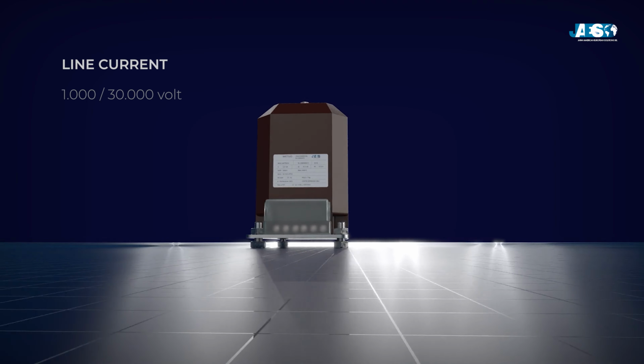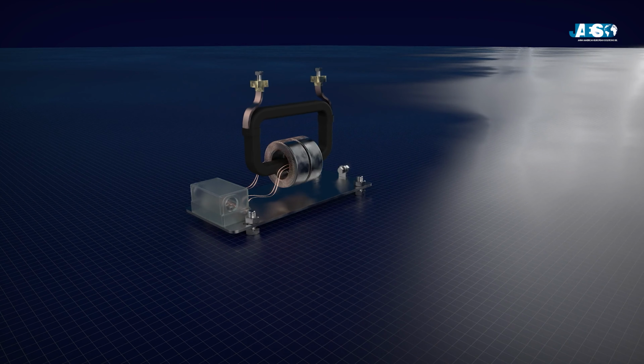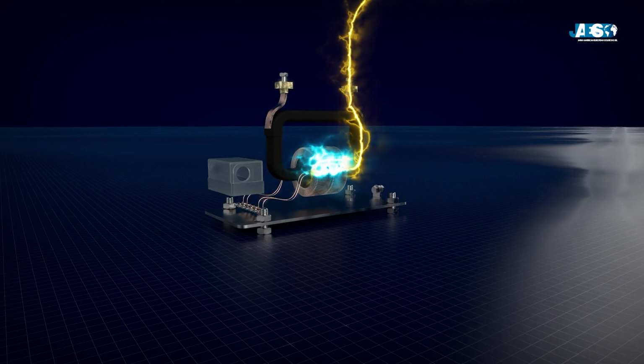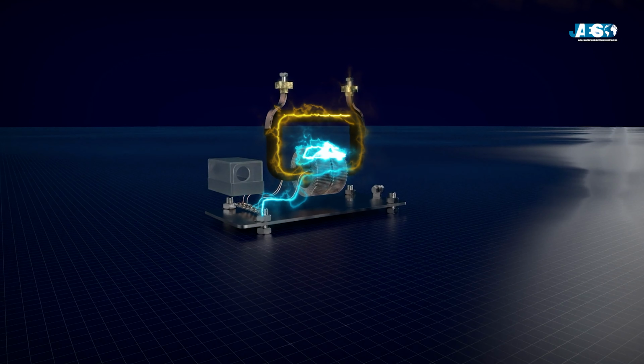They are basically inductive sensors consisting of a primary winding, a magnetic core, and a secondary winding. Essentially, a high current is transformed into a lower one using a magnetic circuit, so very high currents can be measured safely and efficiently. In most CTs, the primary winding has very few turns, while the secondary winding has many more turns. This coil ratio between the primary and secondary winding determines how much the current load is reduced.